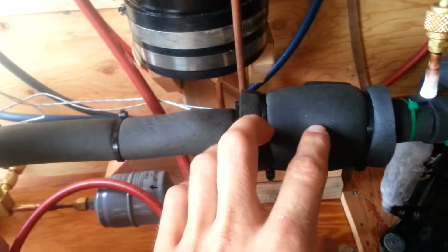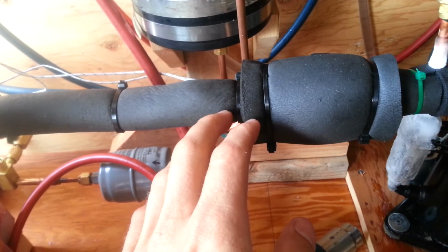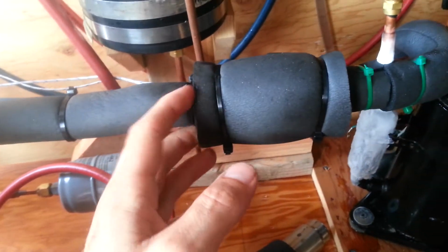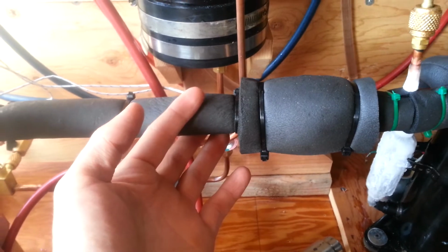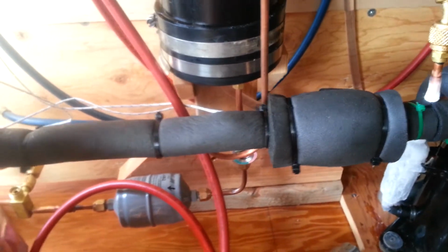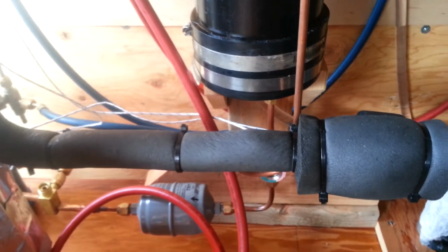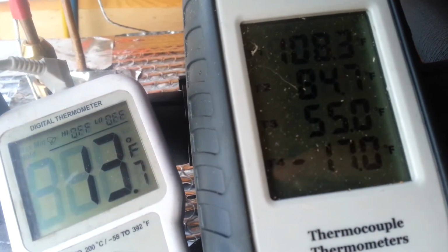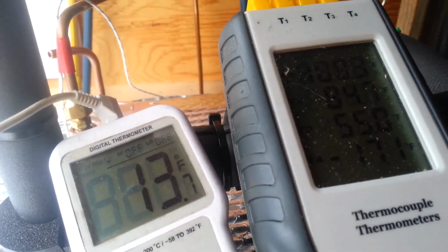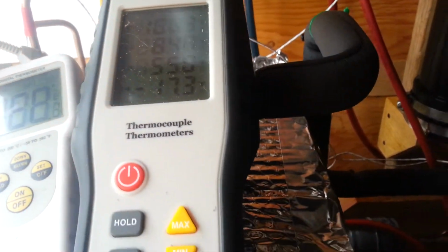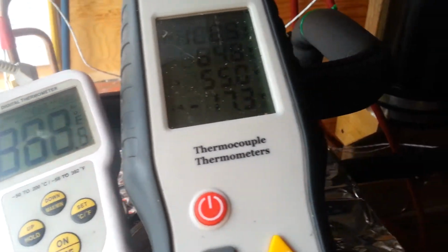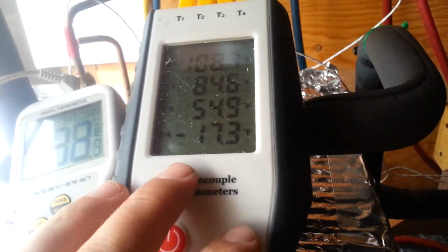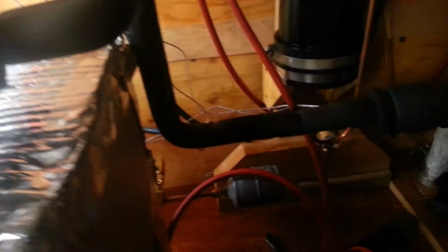One of the reasons for that, the long suction tube, such a low temperature, isn't going to probably read as well. The copper tubing is going to rise in temperature even through this insulation here, but at suction pressures and temperatures above zero, it's almost always within 2 or 3 degrees. -17, what did I say? -23. So yeah, you're talking 5, 6 degrees of superheat, if that number is to be trusted. And most people would tell you that that's perfectly reasonable for superheat.